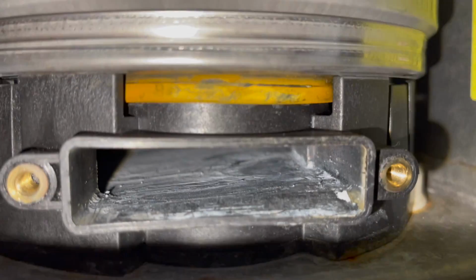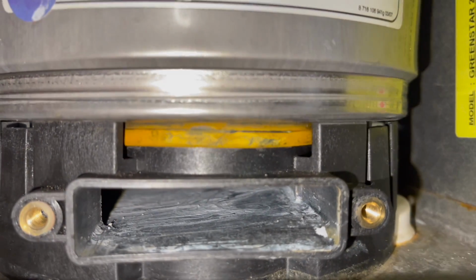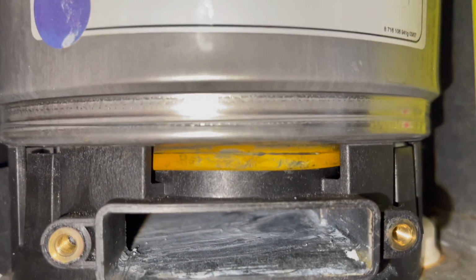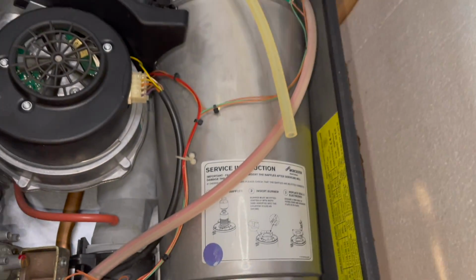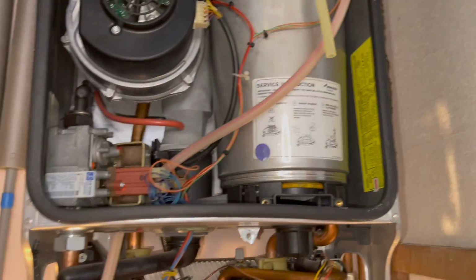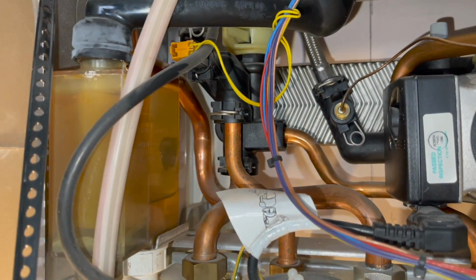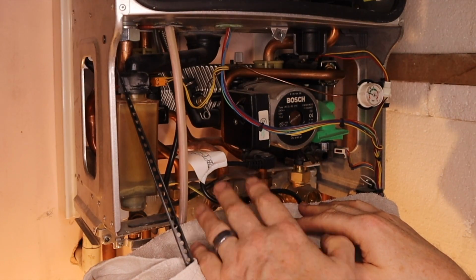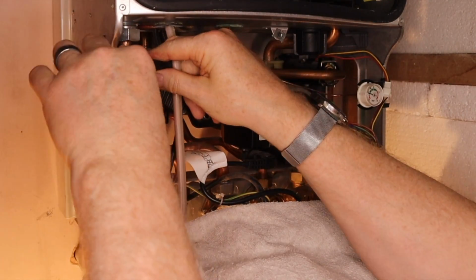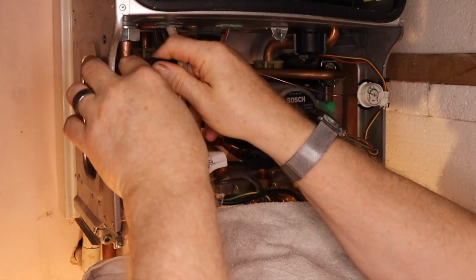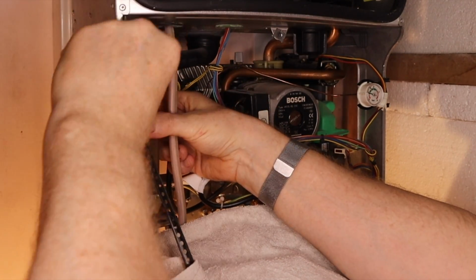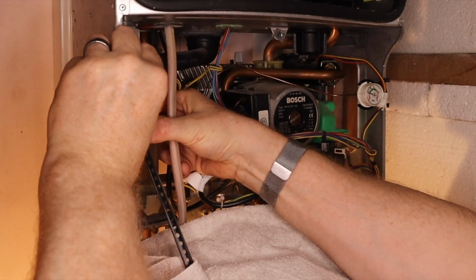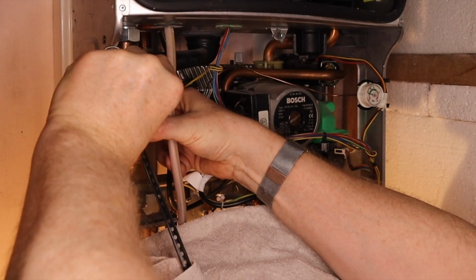Now you can see that's a lot better. Get all the loose bits out with water later when we flush out the heat exchanger. So let's get the trap cleaned out. So I've protected the board with a towel to get this condensate trap out. First thing I need to do is get this rubber pipe disconnected off here, which feels like it's never been off.